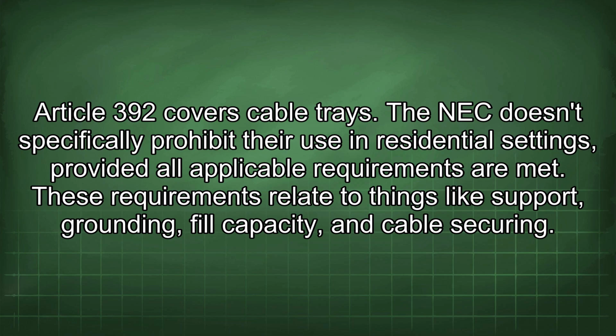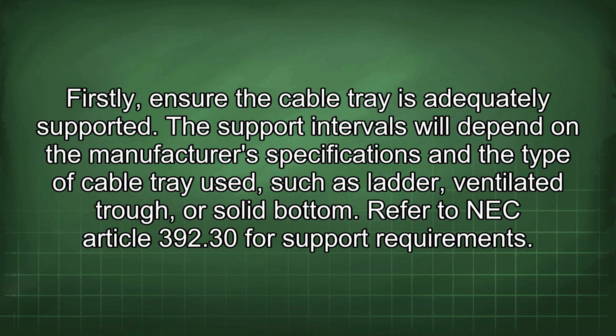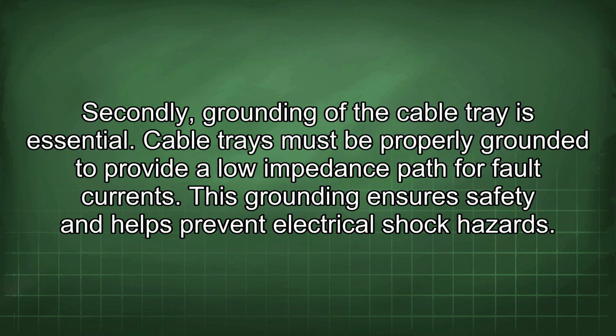The NEC doesn't specifically prohibit their use in residential settings, provided all applicable requirements are met. These requirements relate to things like support, grounding, fill capacity, and cable securing. Firstly, ensure the cable tray is adequately supported. The support intervals will depend on the manufacturer's specifications and the type of cable tray used, such as ladder, ventilated trough, or solid bottom. Refer to NEC Article 392.30 for support requirements. Secondly, grounding of the cable tray is essential.